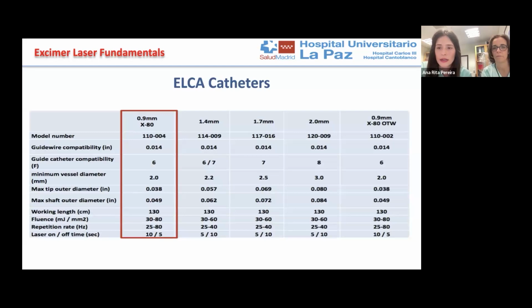Four catheter sizes are available: 0.9, 1.4, 1.7, and 2 millimeters. The 0.9 and the 1.4 millimeter catheters are the most commonly used, with the 0.9 being the preferred catheter in the majority of cases. Importantly, both sizes are compatible with 6 French guide catheters. And of note, ELCA catheters are compatible with any 0.014 guide wire, so this eliminates the need for a specific guide wire. Additionally, it is possible to apply laser with another guide wire, for example, to protect the side branch, which is also different from the other atherectomy techniques.